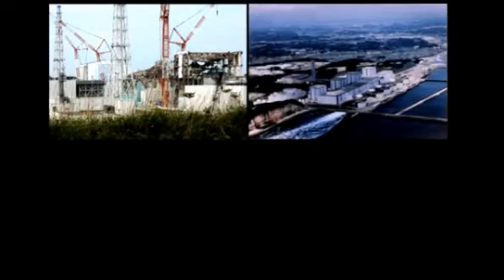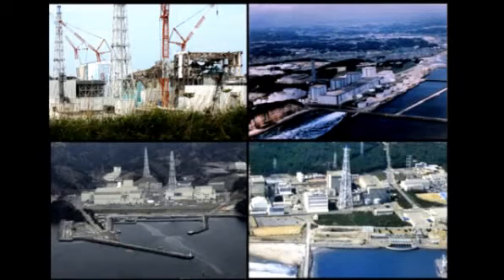So the 9 that failed because they were flooded would have failed anyway because their pumps were destroyed, plus 15 others were destroyed just because they couldn't be cooled. Between the 4 sites, Fukushima Daiichi, Daini, Onagawa, and Tokai, there were 37 diesels. 24 were wiped out by the tsunami.